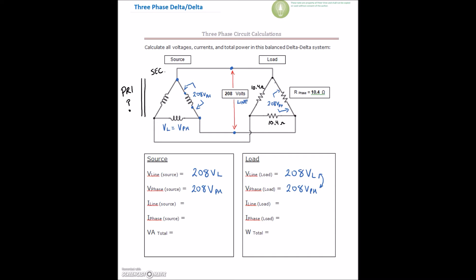Next thing we need to do is we need to take a three-phase circuit and break it down into a single-phase circuit. So we have 208 volts coming over here. That 208 is now impressed across a resistor at 10.4 ohms. So we're going to take a three-phase circuit and break it down. This is our phase value. We're going to break this guy down into a single-phase Ohm's Law circuit.